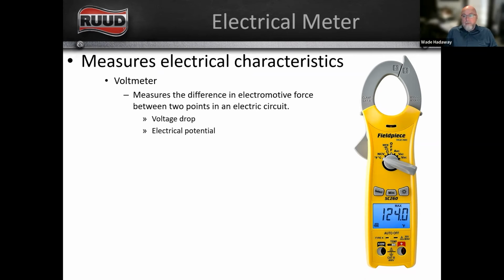So this is an electrical multimeter, and the voltmeter measures the difference in electromotive force between 2 points in a circuit. And we can do that in a couple of different ways. It'll measure voltage drop, and that voltage drop could be because we have too much resistance, or because we are doing some sort of mechanical or electromechanical work, right? When we energize the coil, the energy it takes to create that electromagnetic field causes a voltage drop. We could also have a voltage drop if we have a wire nut that's not very tight, or a contactor that's not closing all the way, where the contacts aren't closing all the way, and we can have a drop there. And I'll show you a diagram of that in a second.